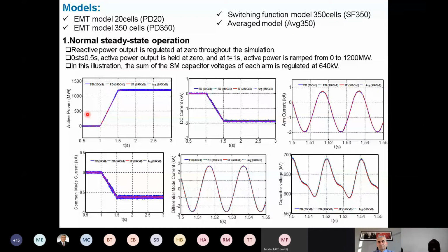This is the DC current of all these models, identical. These are the arm currents of all these models, identical as you expected. And this is the common mode current, where the upper and lower arm of each phase are summed together and divided by 2, and here all are identical, except you can see the MMC with fewer cells shows a little bit more ripple than the one with a large number of cells on average.